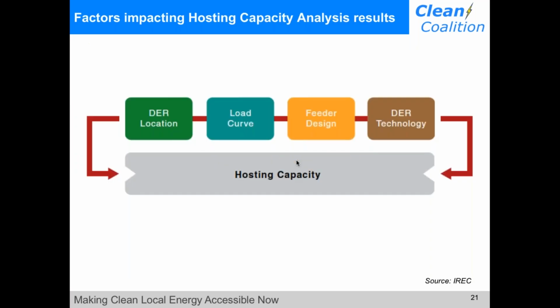The results of the hosting capacity analysis depend on a variety of factors. For example, the location of a line segment often affects the hosting capacity. A line segment near a substation can often handle more local generation than one at the end of a long feeder, which has to do with the physical limitations, thickness, and gauge of those lines. The unique characteristics of a circuit's existing load profile, as well as its design, also impact the hosting capacity analysis results.